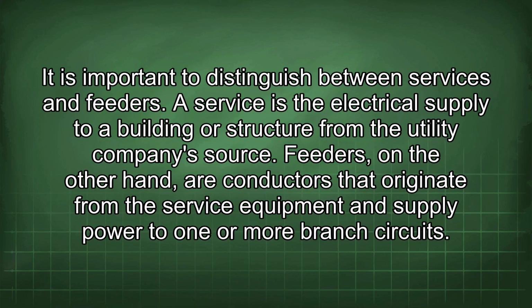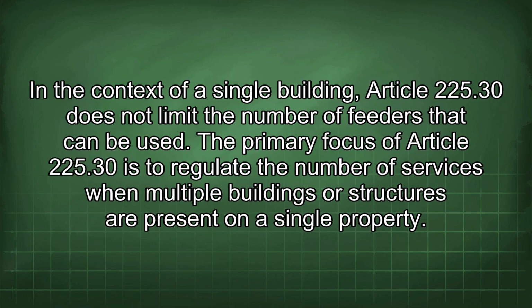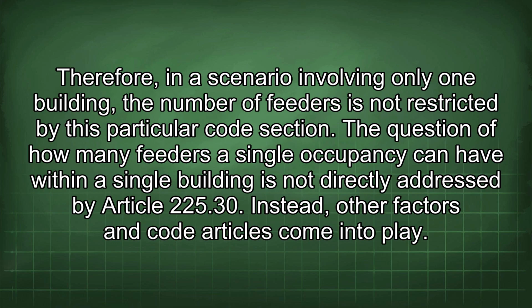It is important to distinguish between services and feeders. A service is the electrical supply to a building or structure from the utility company source. Feeders, on the other hand, are conductors that originate from the service equipment and supply power to one or more branch circuits. In the context of a single building, Article 225.30 does not limit the number of feeders that can be used. The primary focus of Article 225.30 is to regulate the number of services when multiple buildings or structures are present on a single property. Therefore, in a scenario involving only one building, the number of feeders is not restricted by this particular code section.